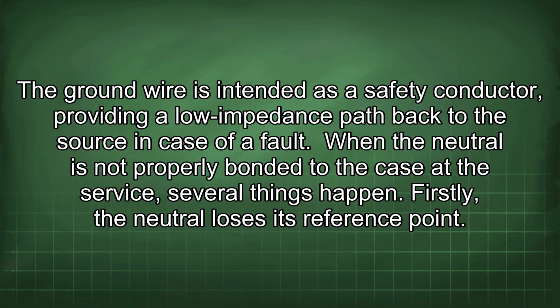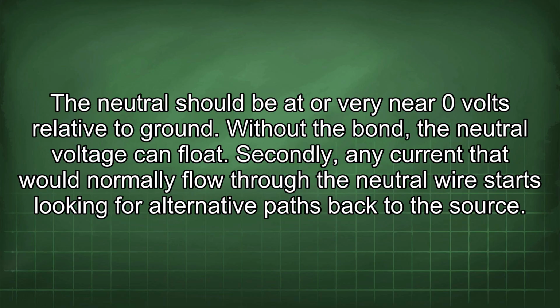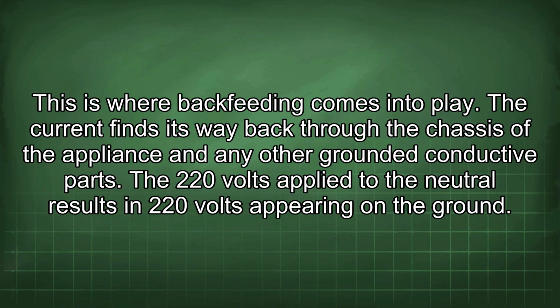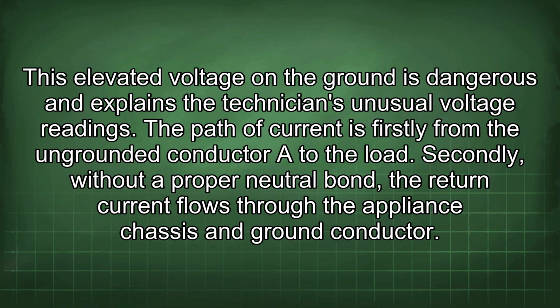When the neutral is not properly bonded to the case at the service, several things happen. Firstly, the neutral loses its reference point. The neutral should be at or very near 0 volts relative to ground. Without the bond, the neutral voltage can float. Secondly, any current that would normally flow through the neutral wire starts looking for alternative paths back to the source. This is where backfeeding comes into play. The current finds its way back through the chassis of the appliance and any other grounded conductive parts. The 220 volts applied to the neutral results in 220 volts appearing on the ground. This elevated voltage on the ground is dangerous and explains the technician's unusual voltage readings.